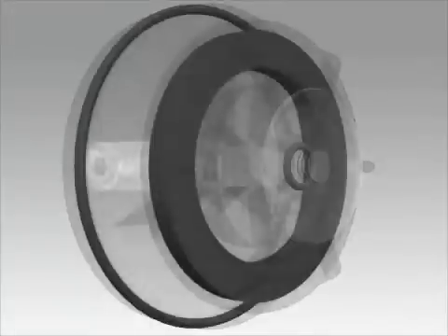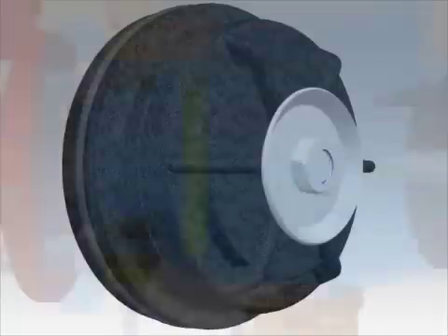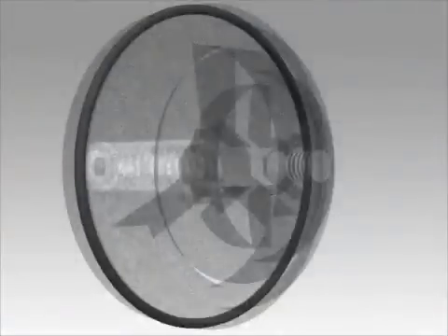If you are installing a repair kit, replace the seal ring, seat o-ring, and stem o-ring. Reassemble the check and tighten the retainer nut. Clean and inspect the o-ring sealing area in the body. Next you will lubricate the seat o-ring.